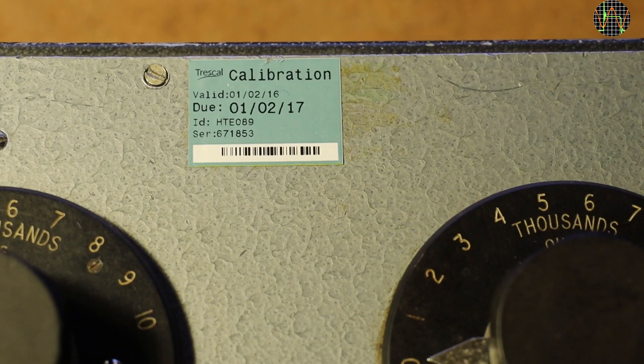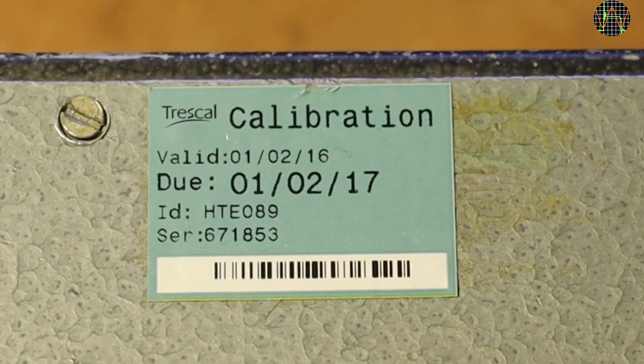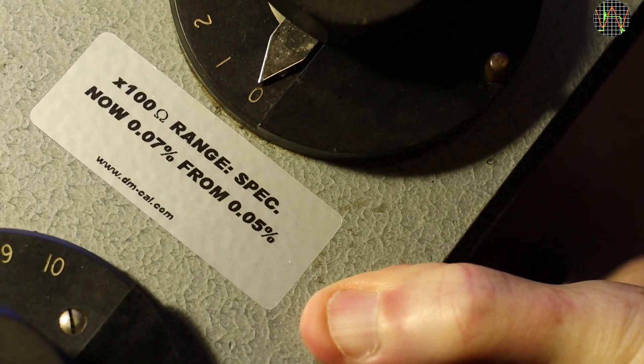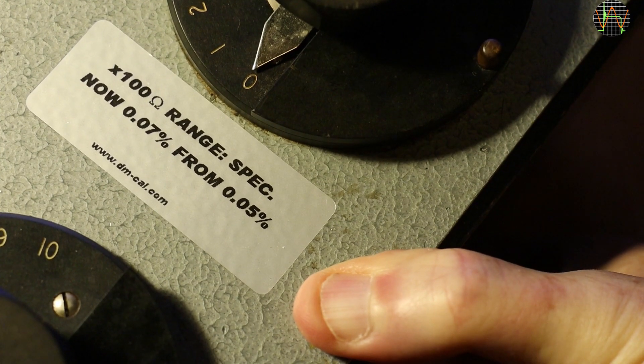That this is a high quality item is further suggested by the Cal sticker. It looks like this box was kept in calibration until relatively recently, given its vintage status — it was obviously worthwhile doing that. A second sticker is also good news. The 100 ohm range was found slightly worse than 0.05%, but a drop to 0.07% is no big deal for me. Since only the 100 ohm range is mentioned, the other ranges must have still met the 0.05% grade when this calibration was done.